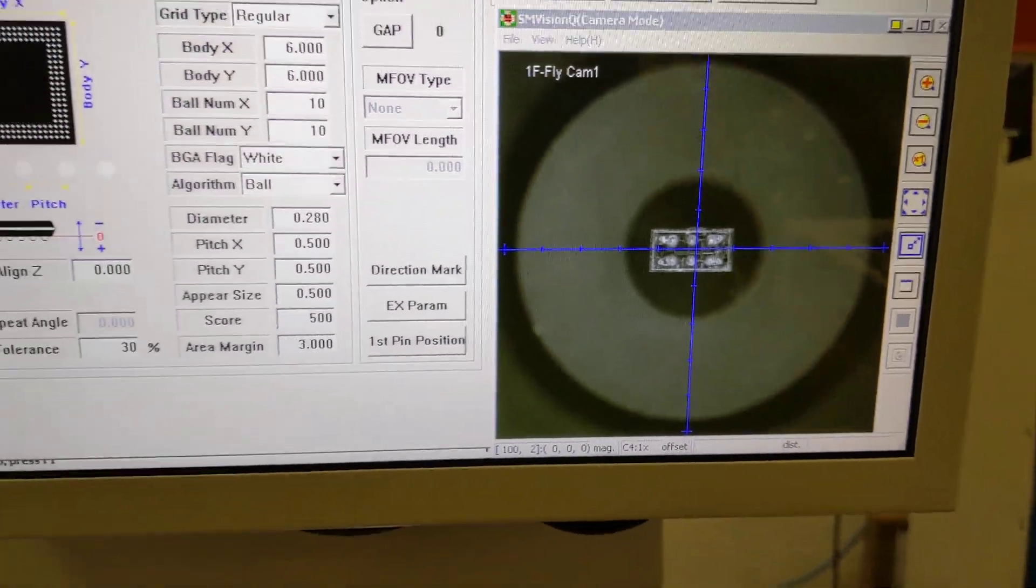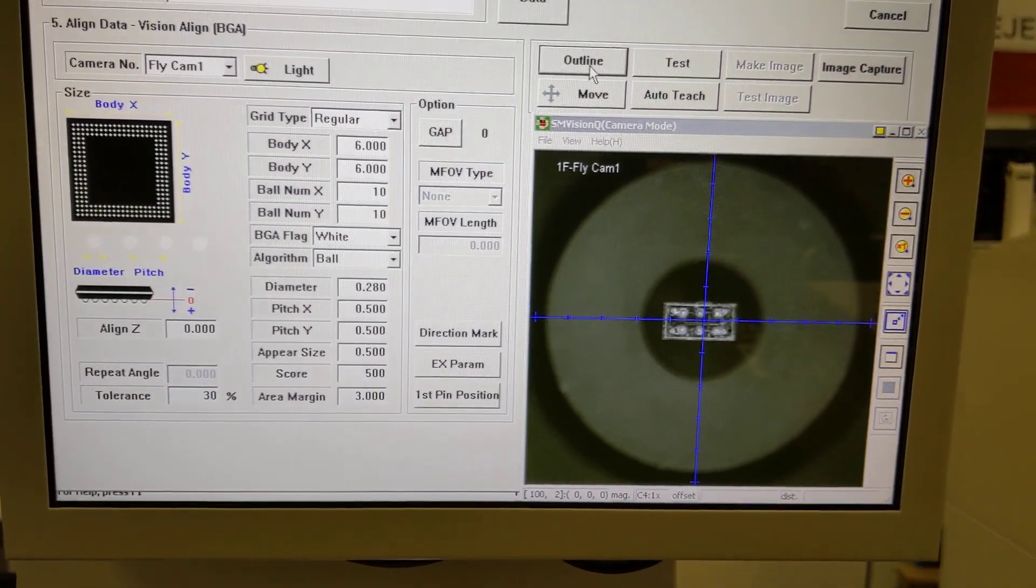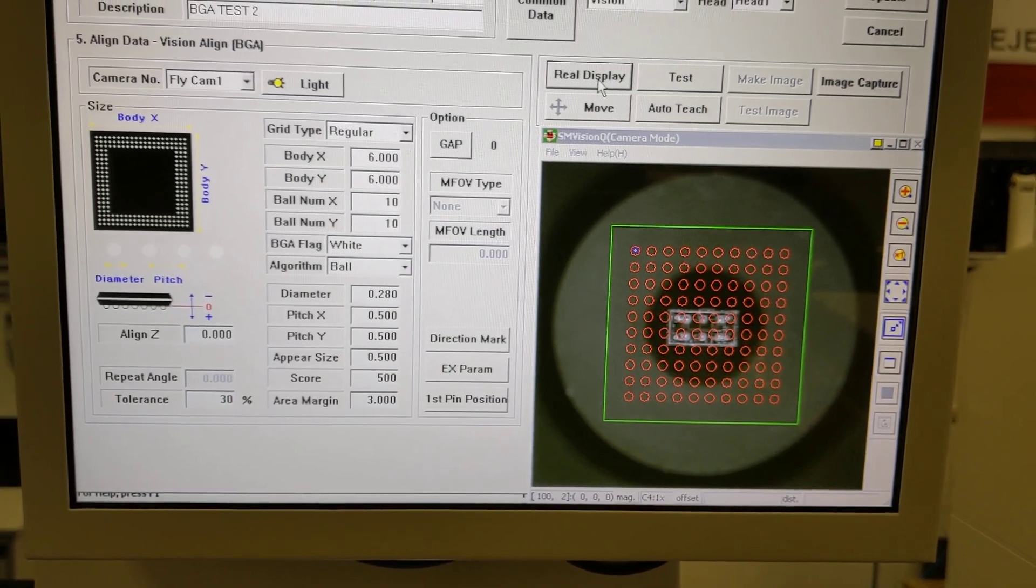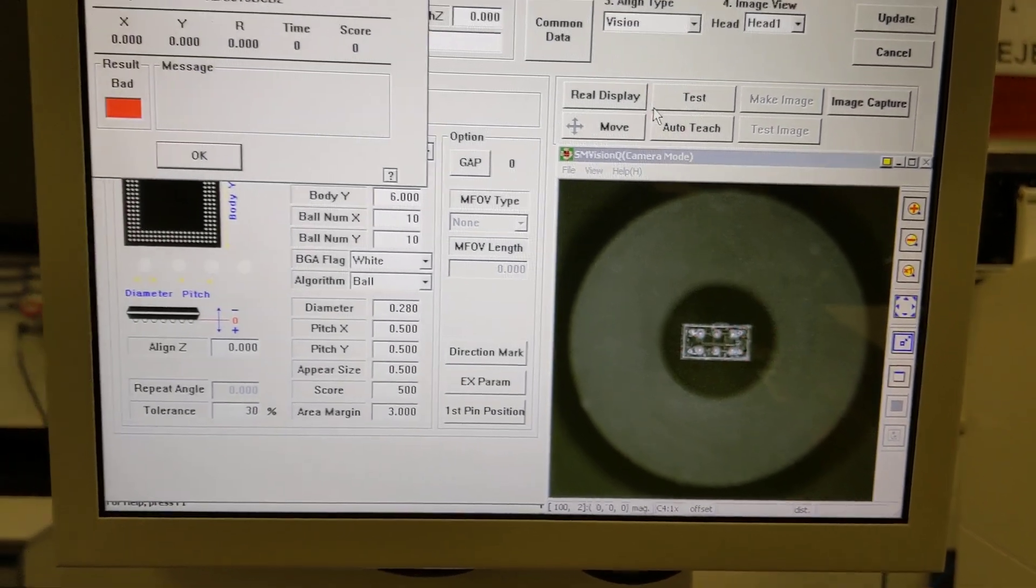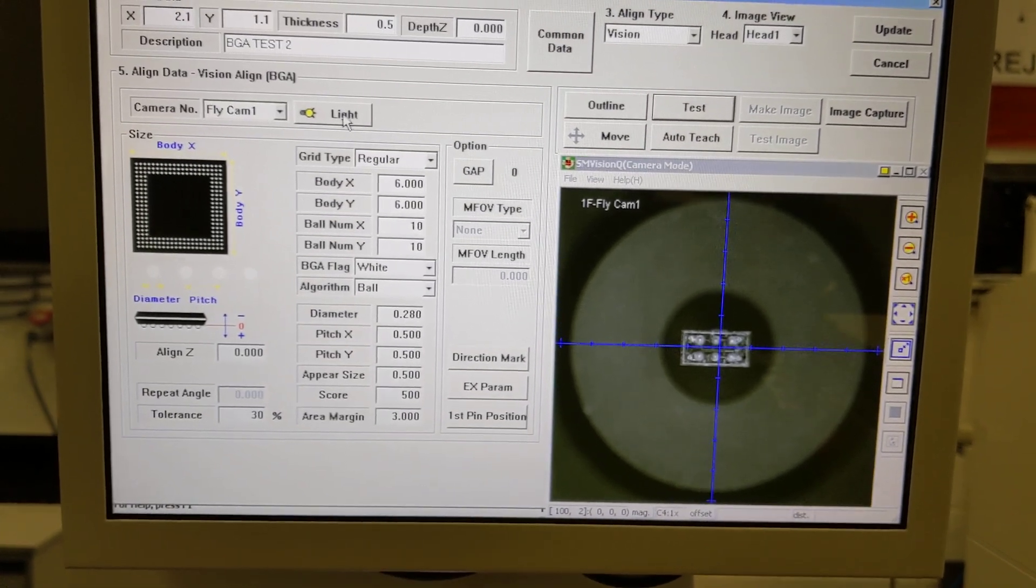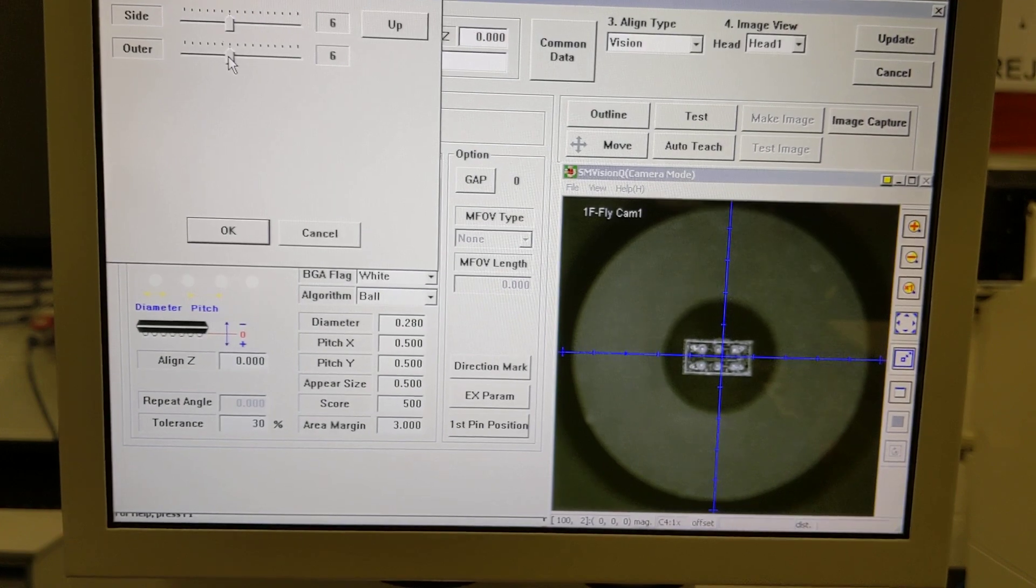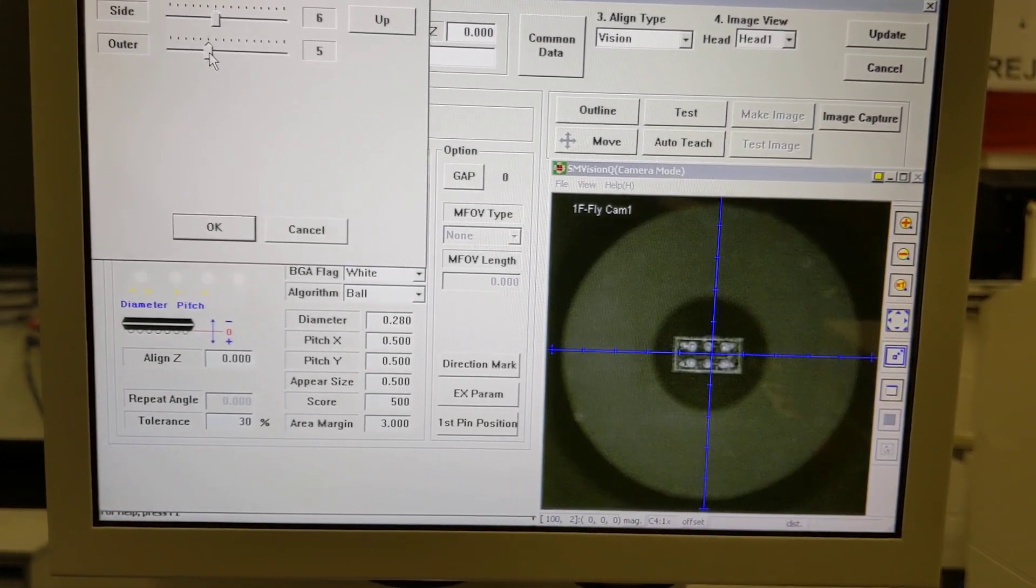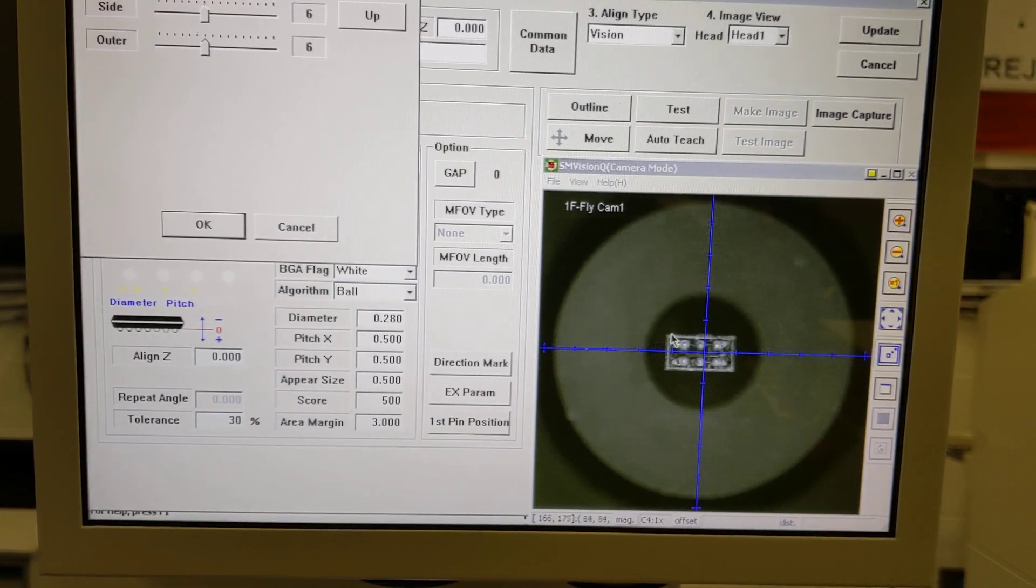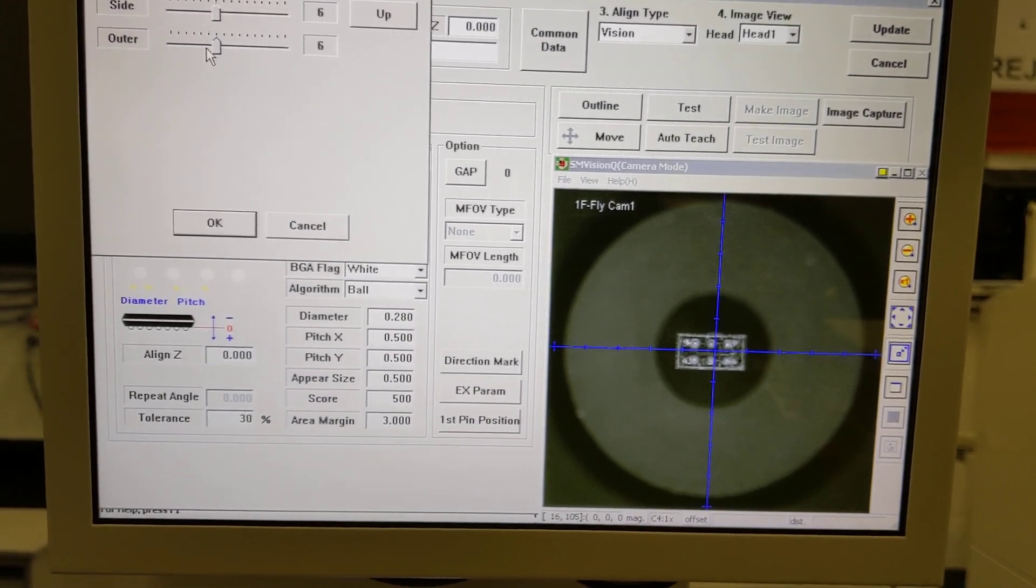So remember this is, at the minute, just looking for this, which is going to fail of course. Okay, so now we're going to change the lights. So BGA, as I say, you only want side lights. You want to get rid of all this stuff here. You don't want to look at the body outline or any of the wire bonds. So I'll switch this off.